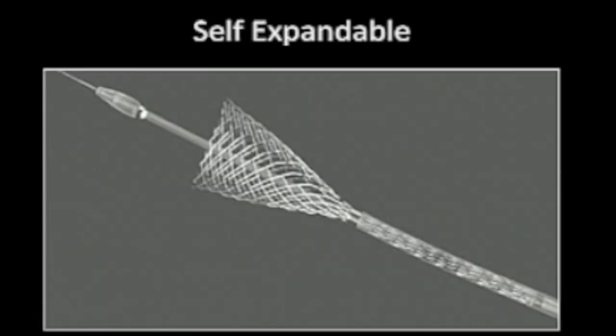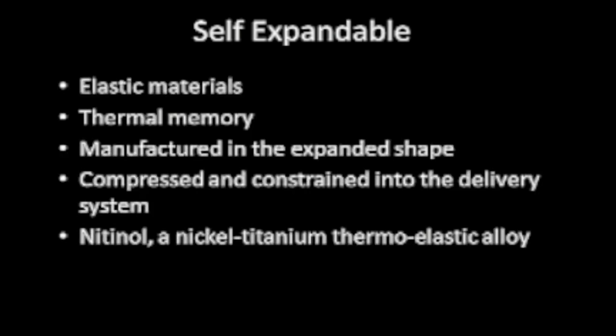A self-expandable stent is designed to go over a wire inside a sheath. As you bring back the sheath, the stent automatically deploys inside the vessel — nothing else is required to open it up. The properties of a self-expandable stent include elastic materials with thermal memory: when manufactured, it's made at a temperature that causes it to automatically return to that same design when deployed in the vessel. Most are made of nitinol — nickel-titanium — a thermo-elastic alloy.